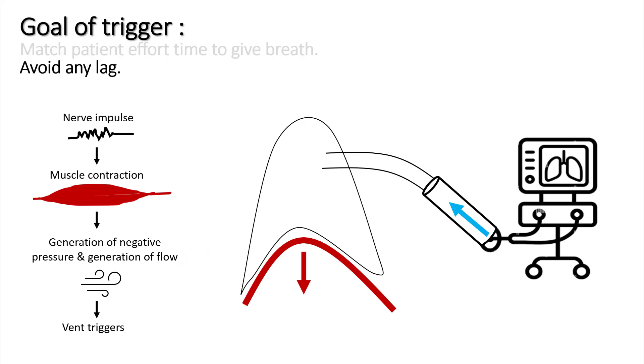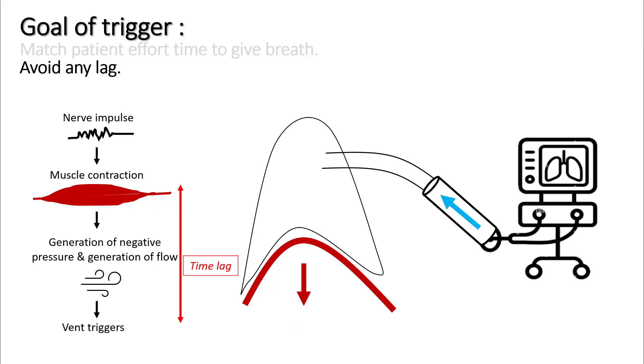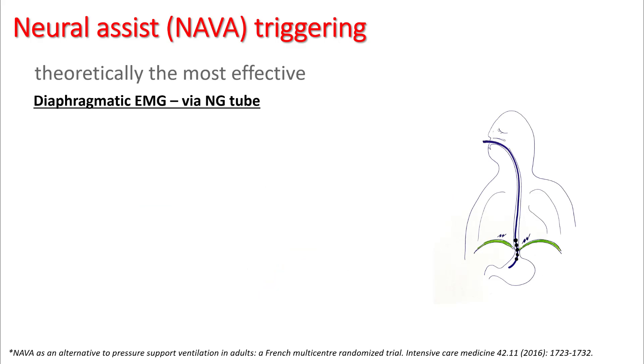The second goal is to avoid any lag. The stimulus for breathing comes from nerve impulses from the brain, which results in muscle contraction, which results in negative pressure, then generation of flow — and that's what is sensed by the ventilator. So there's a time lag between muscle contraction and before the machine gives the breath. Because of this time lag, the patient can have some discomfort in breathing. An ideal trigger avoids any lag — meaning anytime your muscle contracts, the machine gives you the breath at the same time. For this, neural assist triggering was invented.